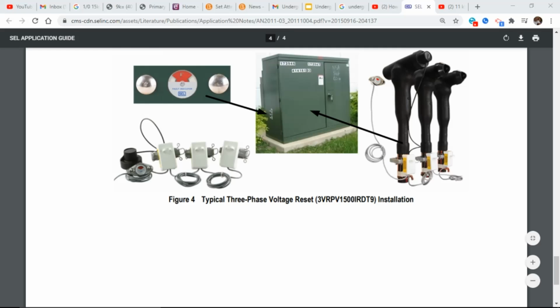Also, you've got to watch out for the indicator. They have become a lot better. It takes a certain amount of current for it to go back to neutral. Current must exist on the cable for it to reset. Now, obviously, if this trips from a fault and you fix the problem, what do you want this flag to do? Go down. So there's a minimum amount of current that's required to make it go back to normal.